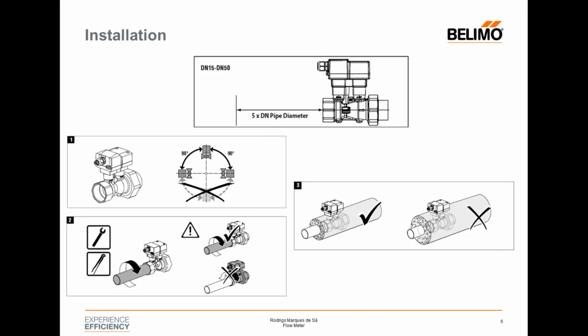About installation, here we see some drawings. As I said, for the inlet length we have to respect 5D before the flow meter; for the outlet, there's no requirement. Also, we cannot install these flow meters upside down - that's another requirement.